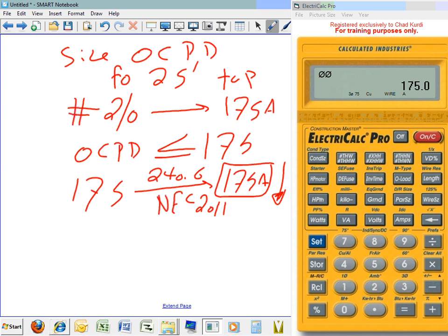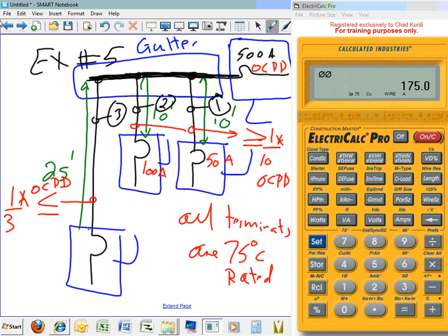Yes, sir. Please, I don't know the rules that you use in the multiplication of the overcurrent protection device's capacity. Right here, these two rules, very easy. Is it a standard rule? That's always a rule. If you're tapping 10 feet, it's 1/10 of the overcurrent protection device. If this was 1,000, and I want to tap a conductor up to 10 feet, that would be 1/10 of 1,000. That will give you 100, and the conductor has to be rated for 100 amp.